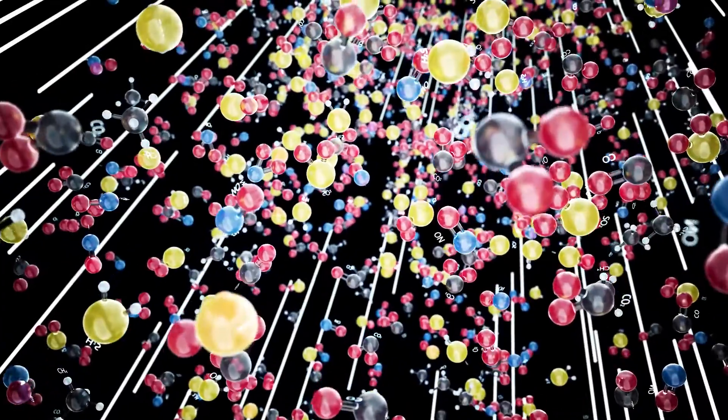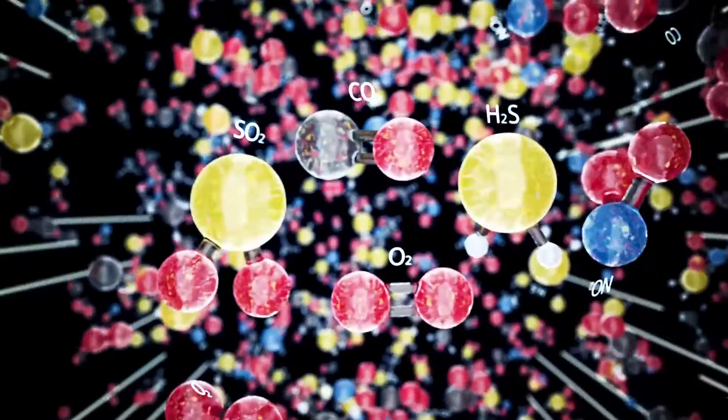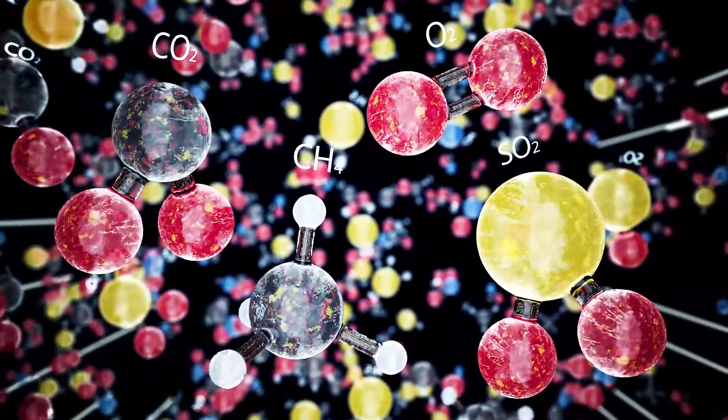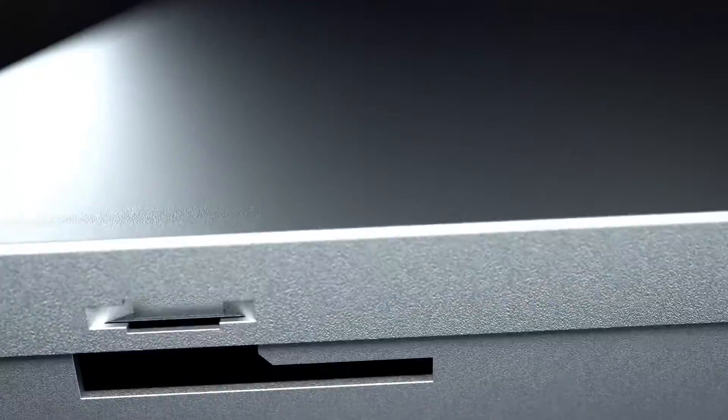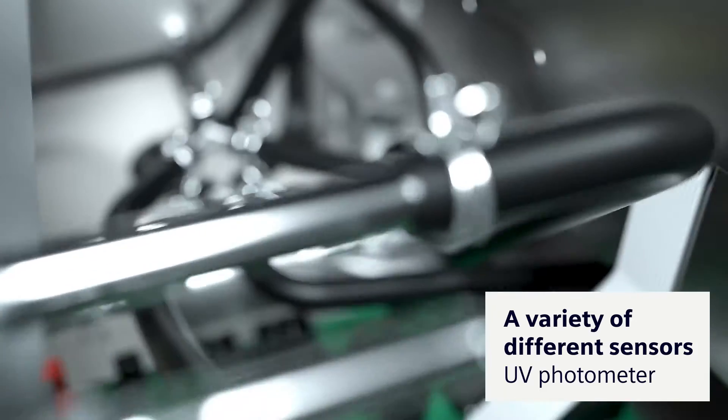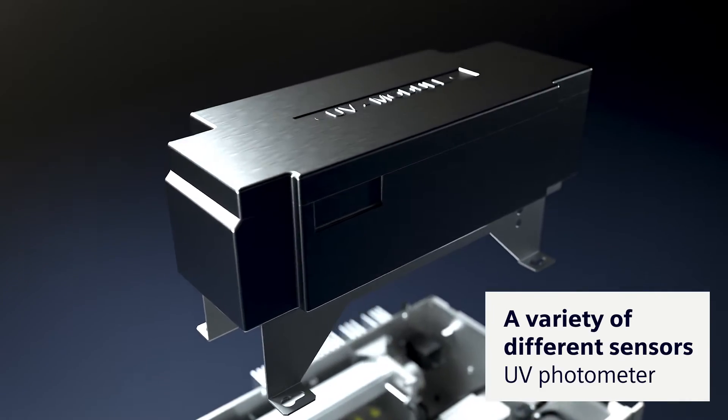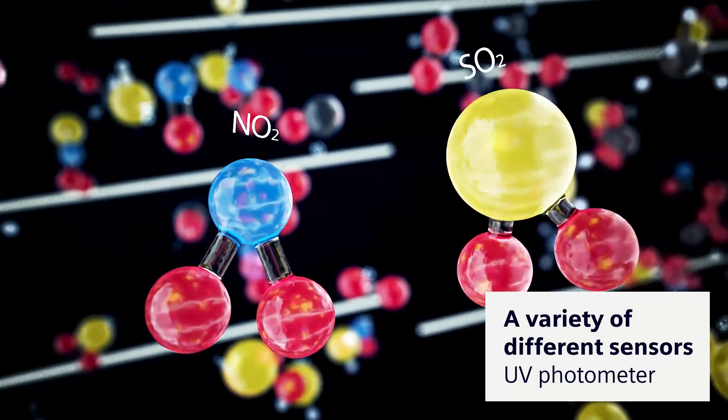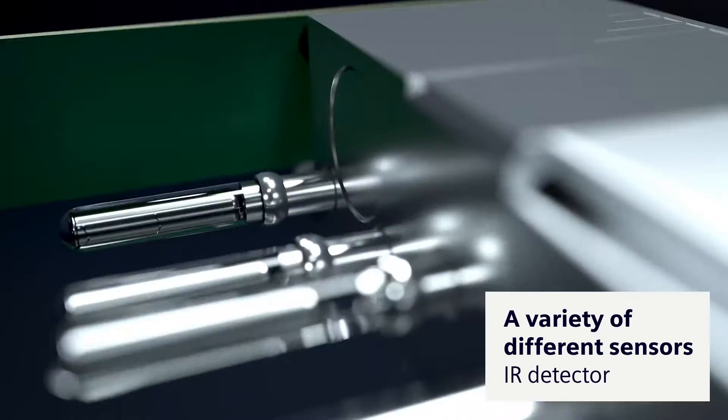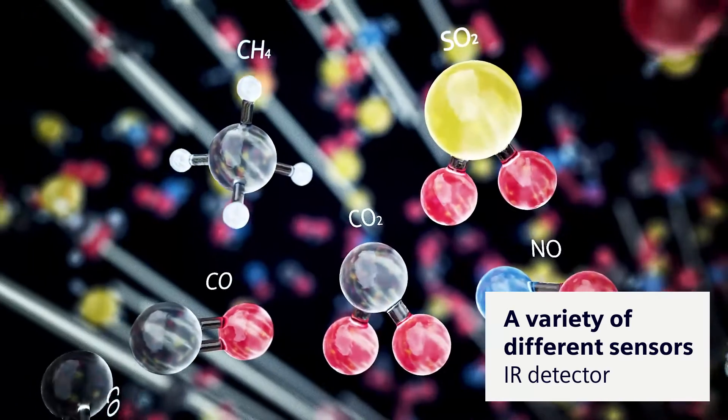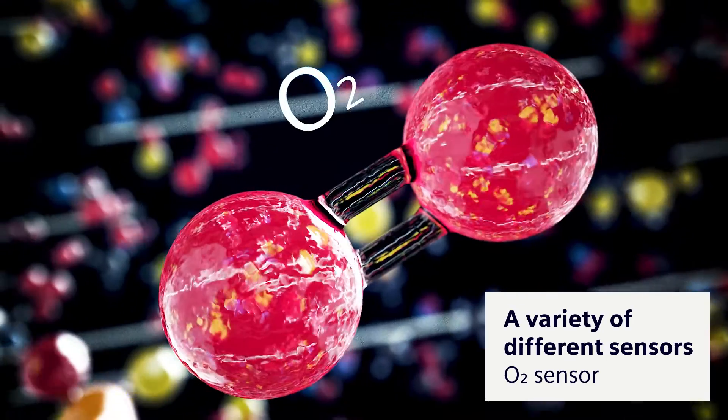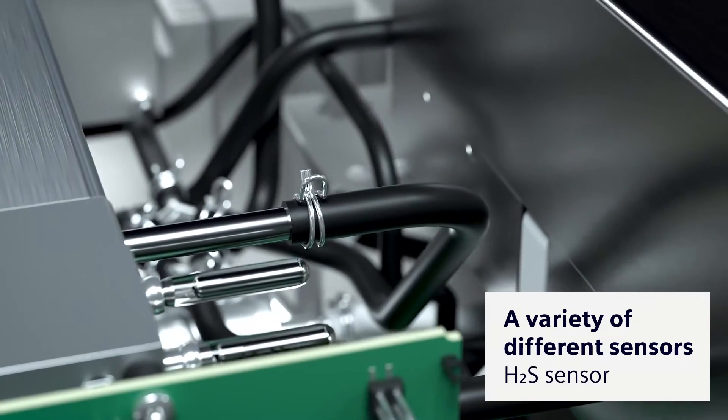The Ultramat 23 can measure 10 components, up to four simultaneously, and can be equipped with a variety of different sensors, like the UV photometer for UV active gases, the IR detector for IR active gases, the O2 sensor, or the H2S sensor.